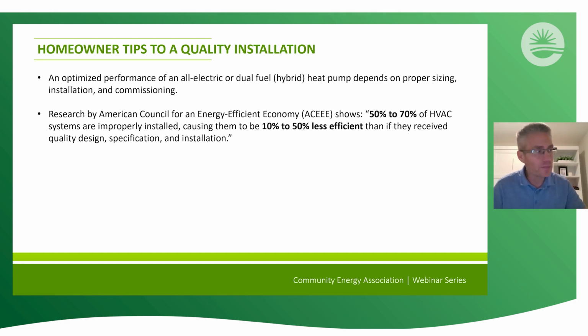It's funny when we do quality assurance and field reviews with homeowners, and we ask, did the contractor do a load calculation? And they ask, what is a load calculation? And we ask, did they verify the performance and show you a commissioning sheet? And it's like, what's a commissioning sheet? These should all be common practice, so the homeowners know that the contractor has done their due diligence when it comes to selecting, installing, and then handing over the equipment to the homeowner.